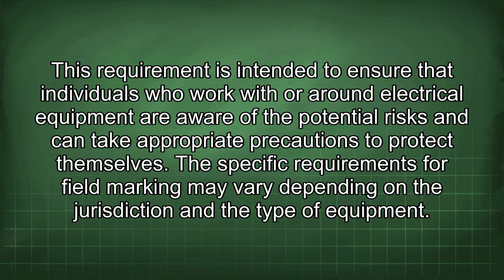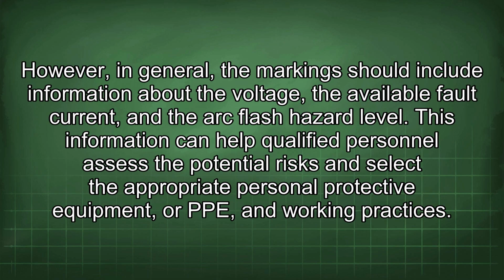The specific requirements for field marking may vary depending on the jurisdiction and the type of equipment. However, in general, the marking should include information about the voltage, the available fault current, and the arc flash hazard level. This information can help qualified personnel assess the potential risks and select the appropriate personal protective equipment, or PPE, and working practices.